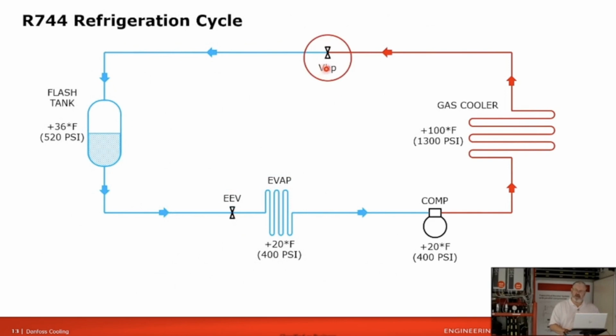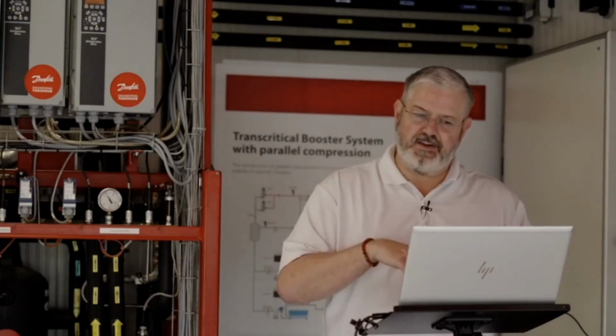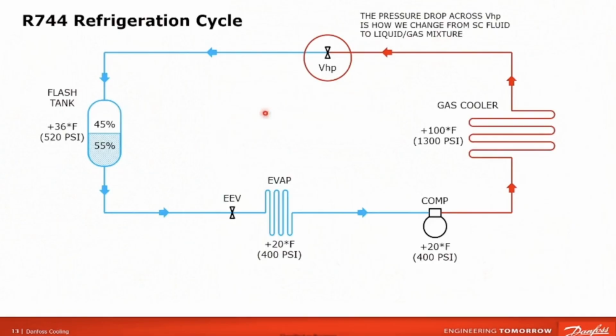So we call that valve high pressure. The pressure drop across that valve is what takes us from the high pressure, 1,300 pounds, back down into the dome so that we can have liquid. Now we referenced a 100-degree ambient day. In that condition, it takes 45% of the refrigerant to flash off and cool down the remaining refrigerant. That's kind of an issue because it's a sealed system, and that gas coming back from the outlet of the high pressure valve has to go somewhere.